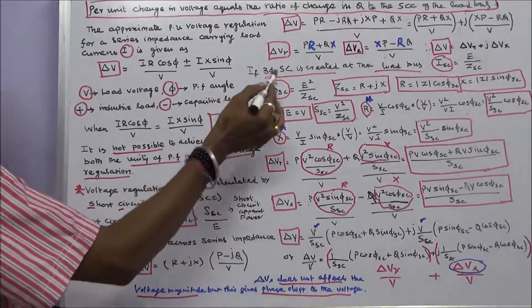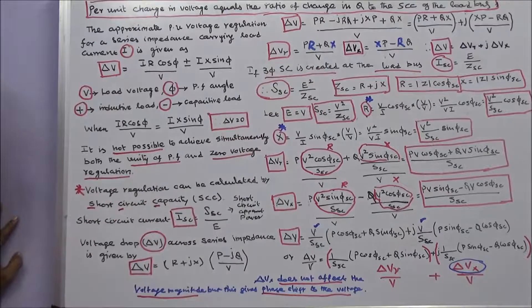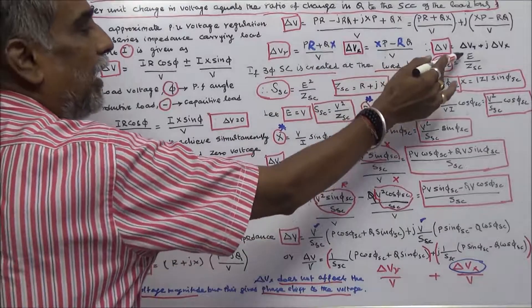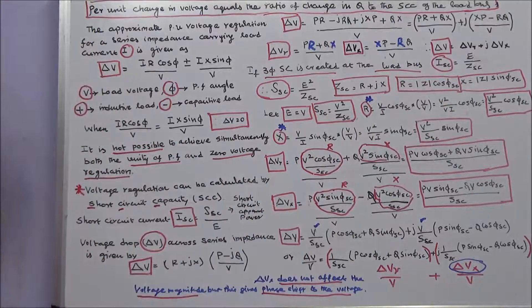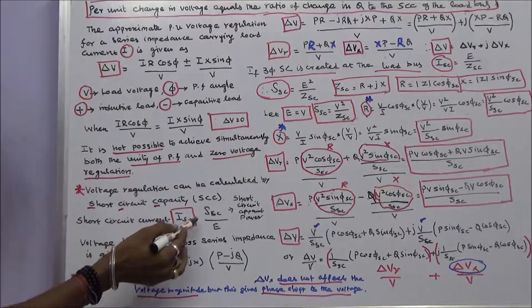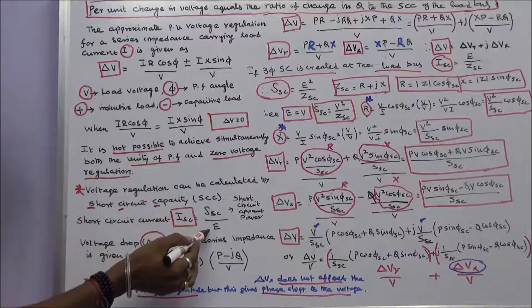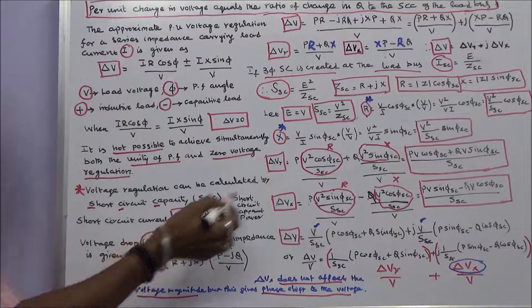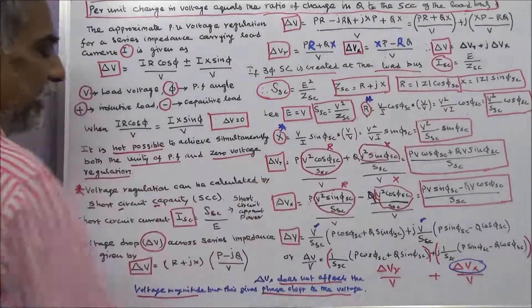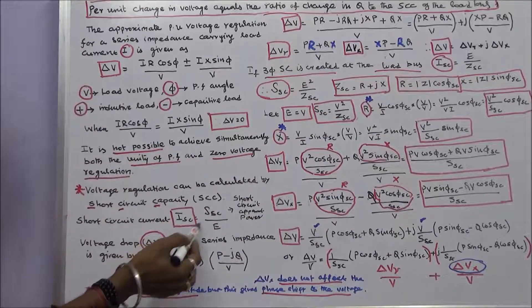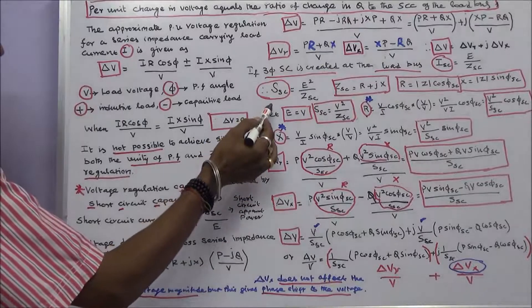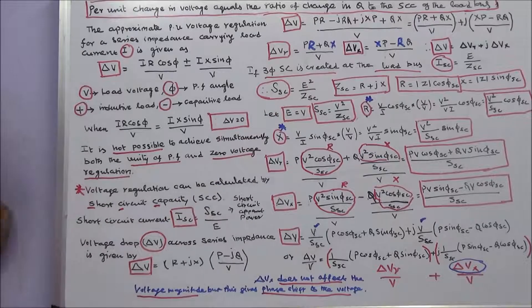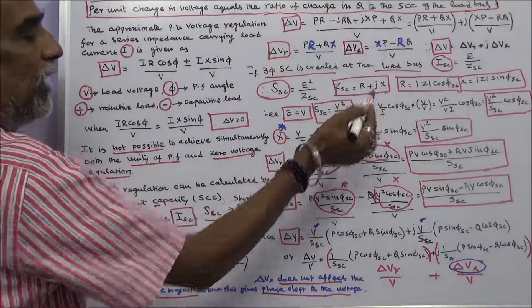If a three-phase short circuit is created at the load bus, the short circuit current ISC equals E divided by the short circuit impedance Z_SC. Also, ISC equals short circuit apparent power divided by E. Substituting, the short circuit apparent power equals E squared divided by Z_SC. The short circuit impedance is equal to R plus jX.